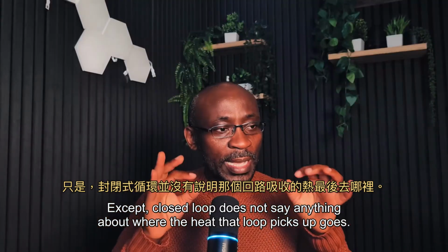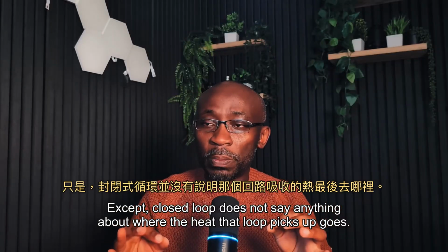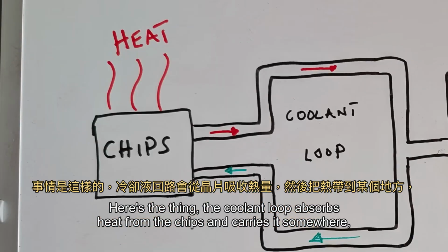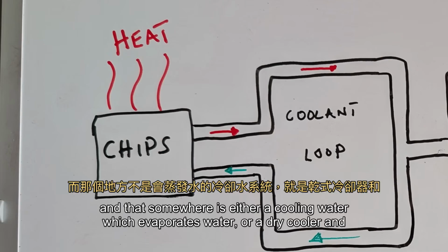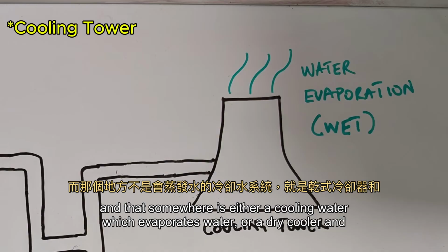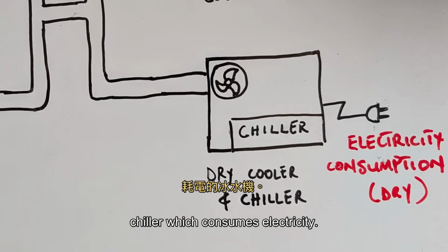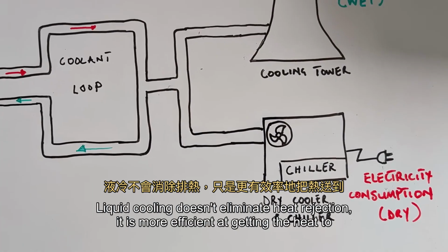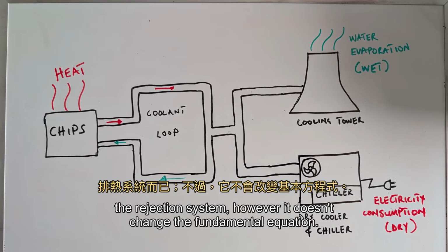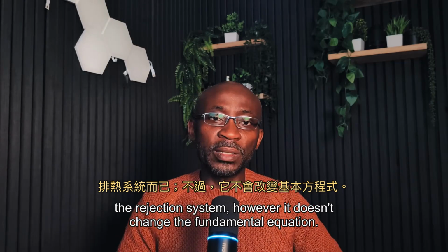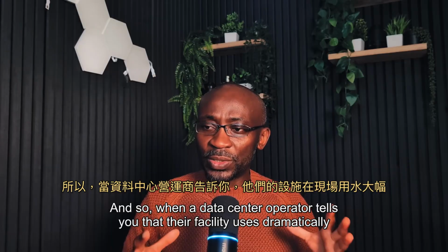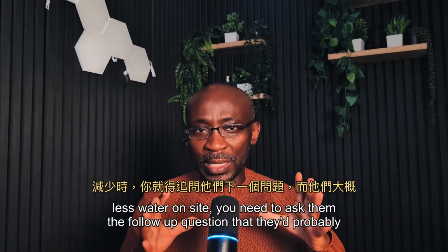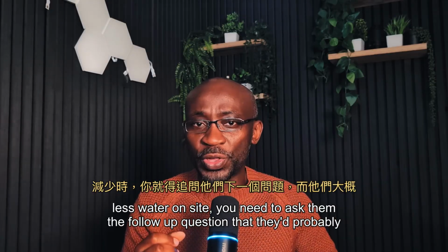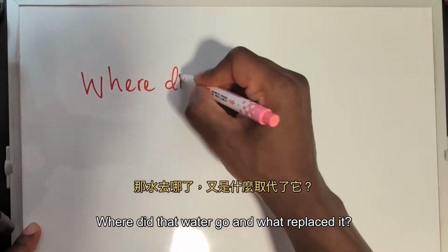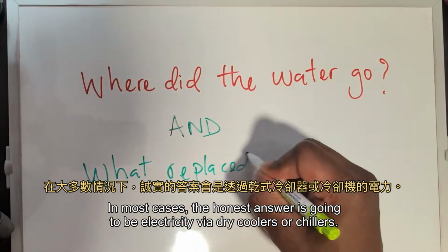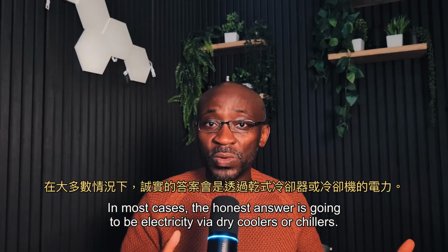Except closed loop does not say anything about where the heat that loop picks up goes. Here's the thing. The coolant loop absorbs heat from the chips and carries it somewhere. And that somewhere is either a cooling tower, which evaporates water, or a dry cooler and chiller, which consumes electricity. Liquid cooling doesn't eliminate heat rejection. It is more efficient at getting the heat to the rejection system. However, it doesn't change the fundamental equation. And so, when a data center operator tells you that their facility uses dramatically less water on site, you need to ask them the follow-up question that they'd probably rather you didn't. Where did that water go and what replaced it? In most cases, the honest answer is going to be electricity via dry coolers or chillers.